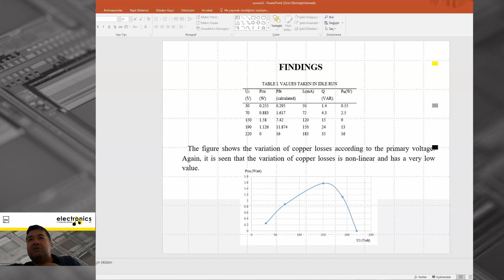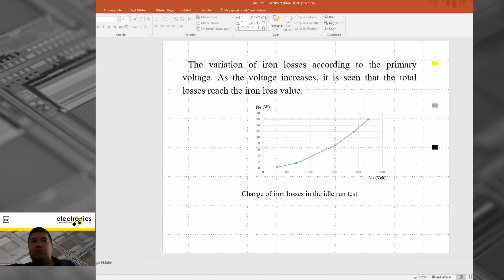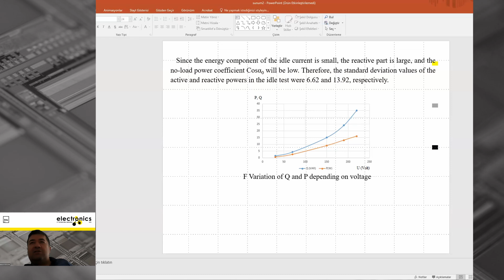The variation of iron losses according to the primary voltage: as the voltage increases, it is seen that the total losses reach the iron loss value. This is the result of the idle run test figure. Since the active component of the idle current is small because of the no load, the reactive part is large and the no-load power factor will consistently be low. Therefore, the standard deviation values of the active and reactive power in the idle test were 6.62 and 13.92 respectively.